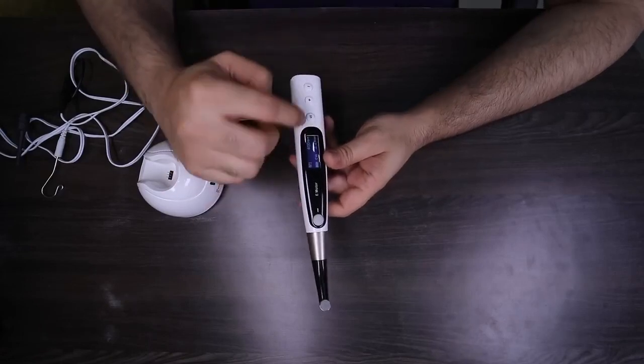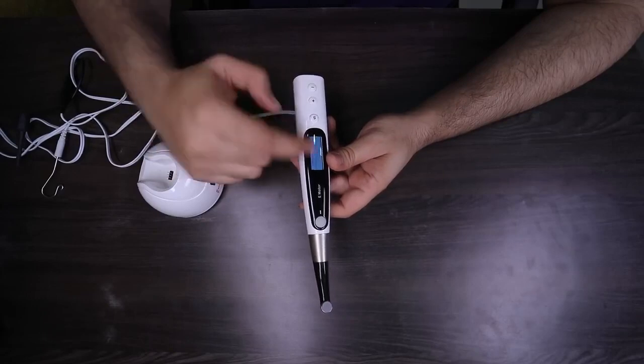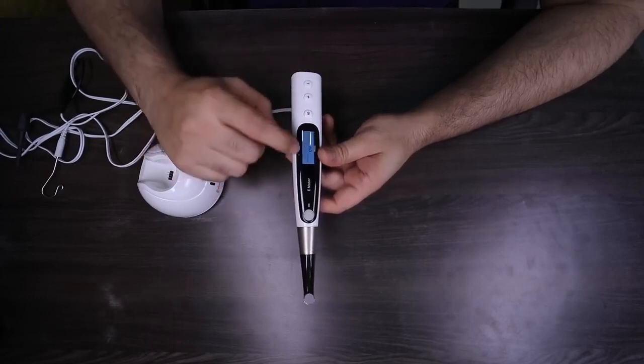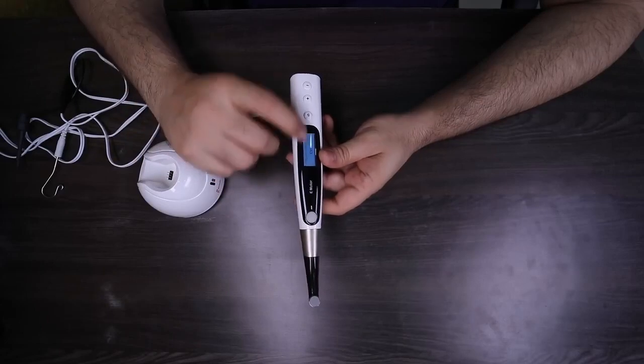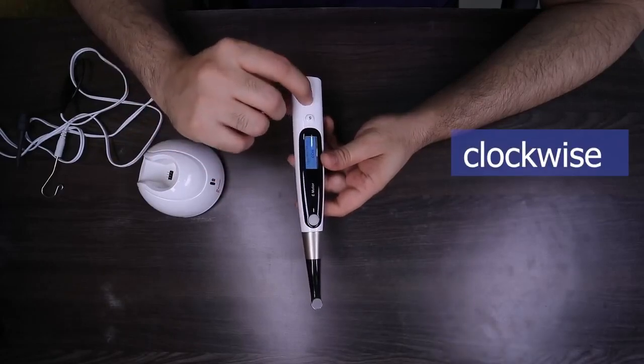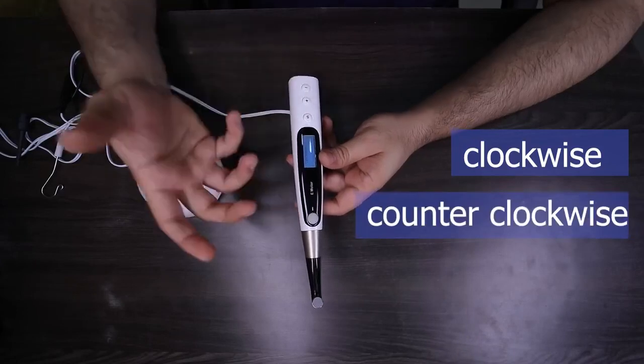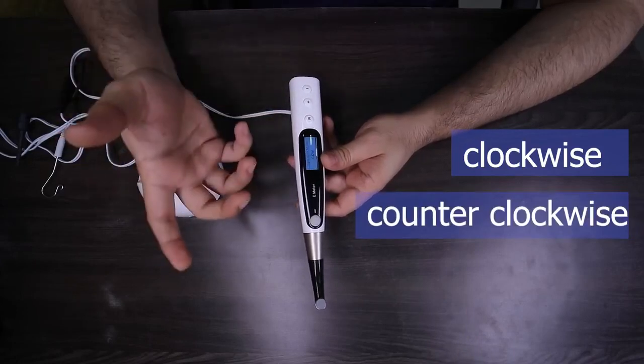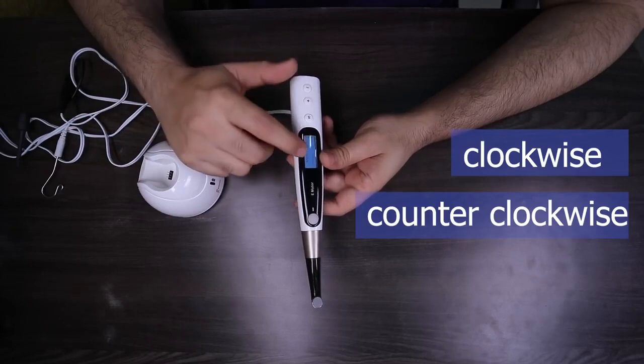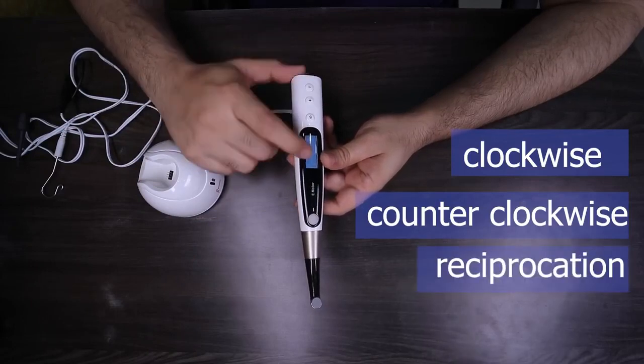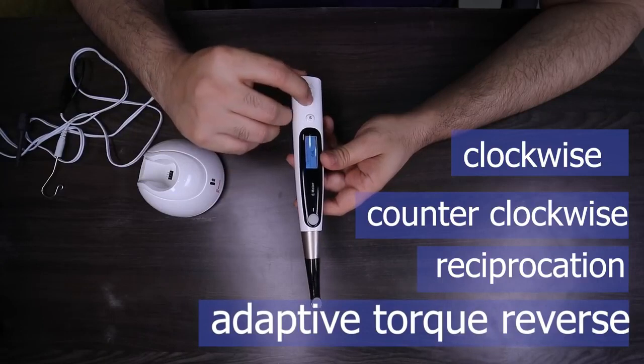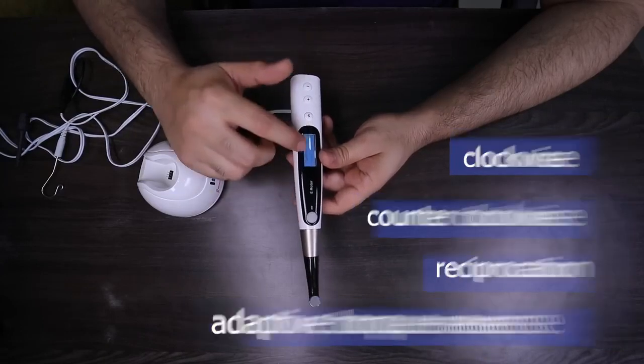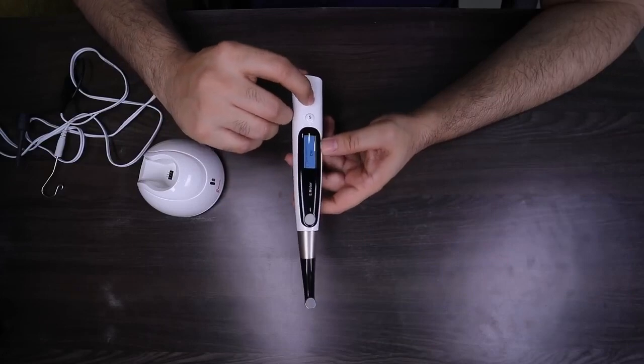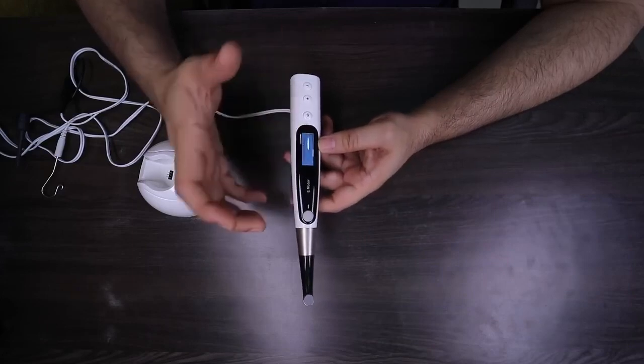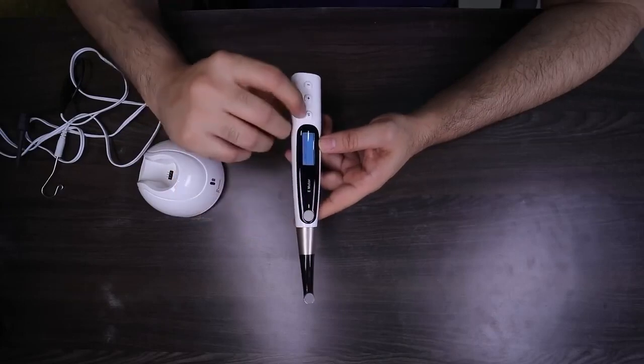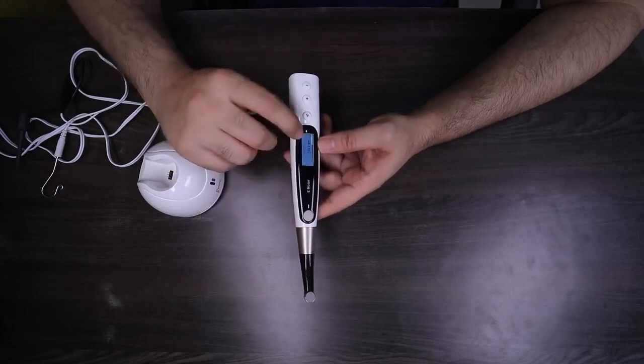Now how do we work? You press the S button, which is the setting button, to go into the operation mode. The operation mode is the rotation motion of the machine, which is a clockwise motion. Pressing the plus or minus button, you shift into a counterclockwise motion. This motion can be used to apply your sealer or your calcium hydroxide. You have a reciprocation motion. You have an adaptive torque reverse. I'll be talking about this. Or you can keep it at preset at your electronic Apex Locator. Once you've decided which mode you want to use, all you do is press the setting button again and you shift to the speed.